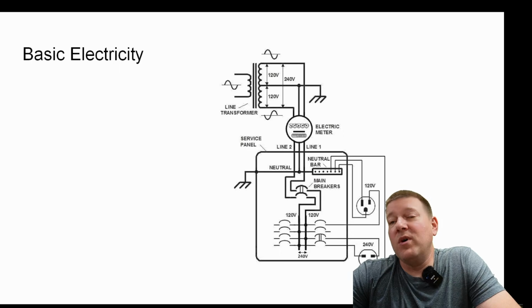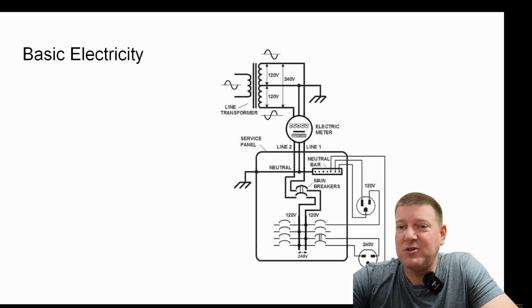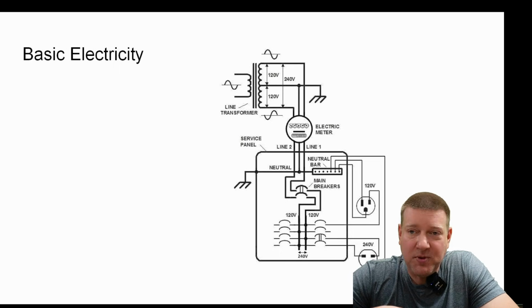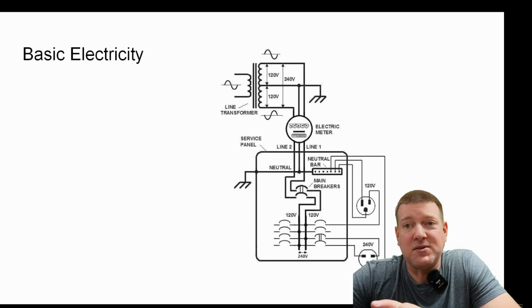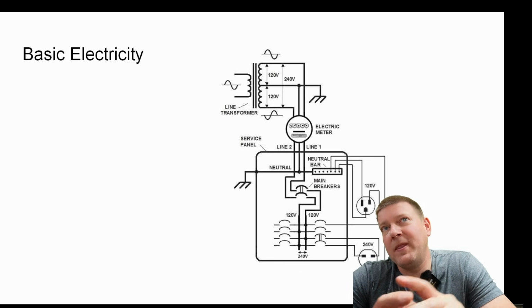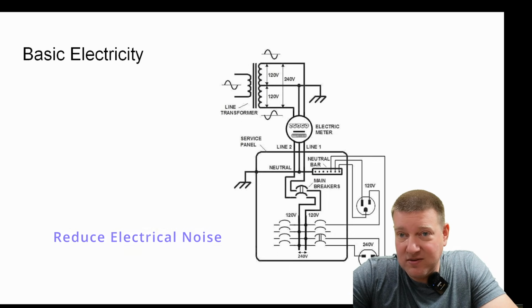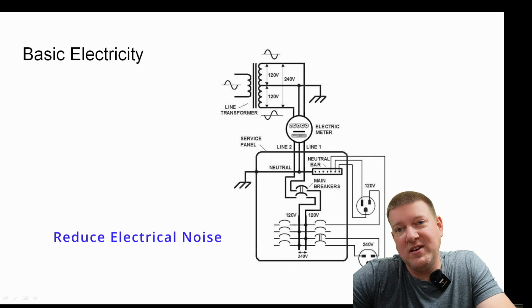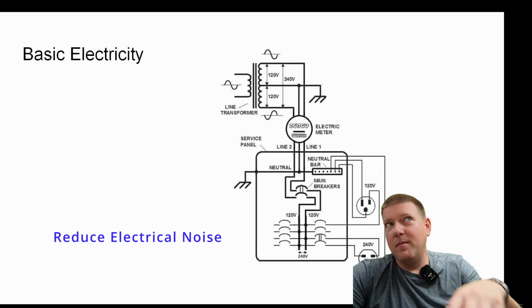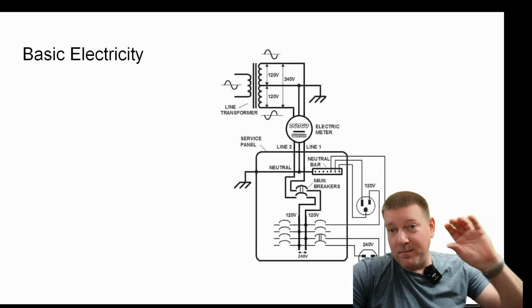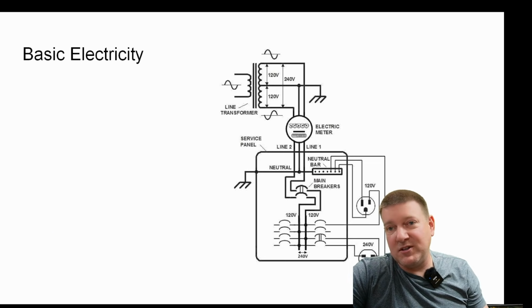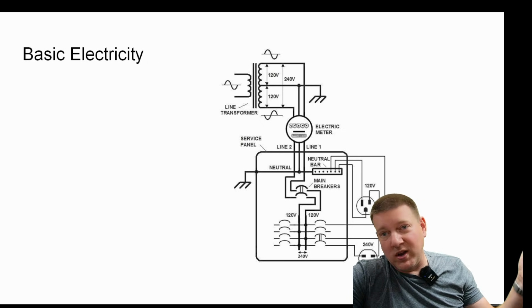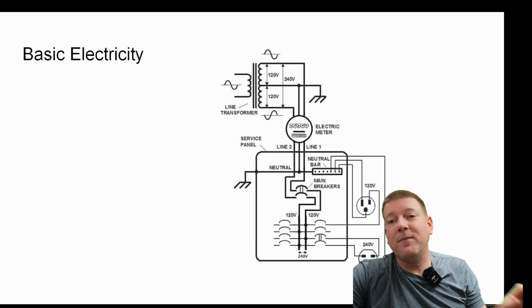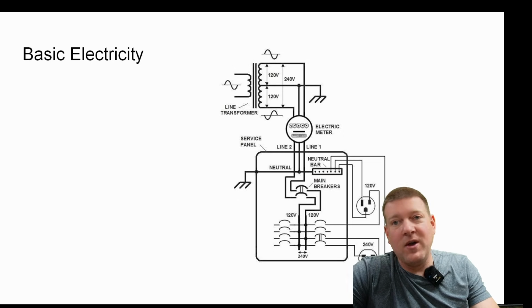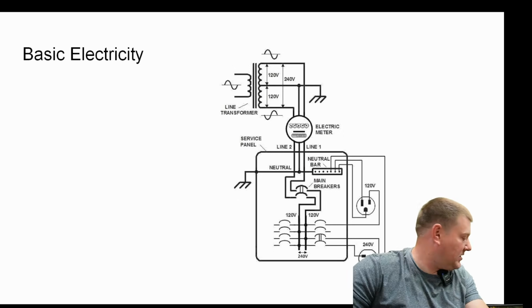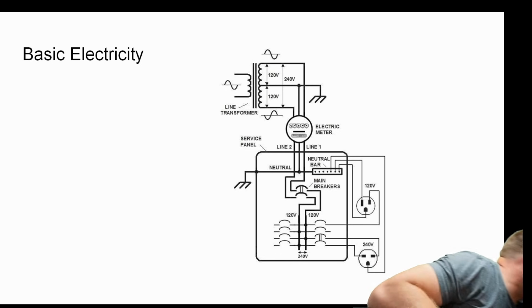And one of the main reasons that we also have ground, especially in hospital systems, and we have redundant grounds, is because that allows us to get rid of noise. Right? All electricity, since it's based on being referenced to ground, all electricity, even noise on an electrical wire, wants to go to ground. So that's why you'll see redundant grounds on medical devices. Matter of fact, I have one right here.